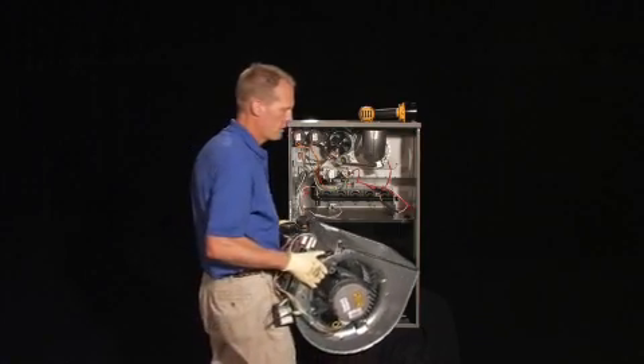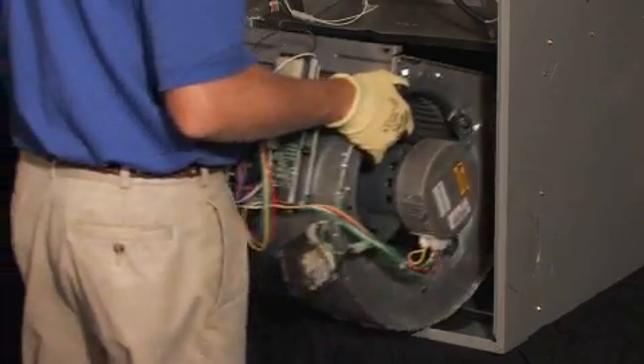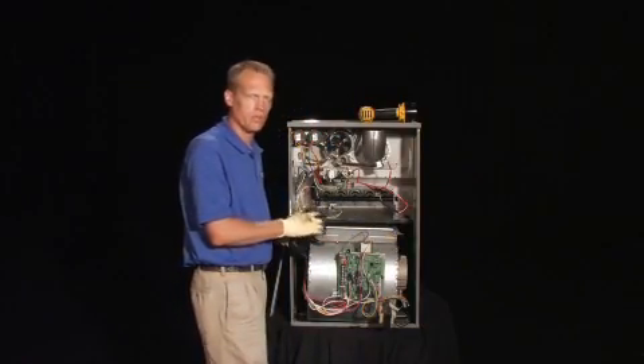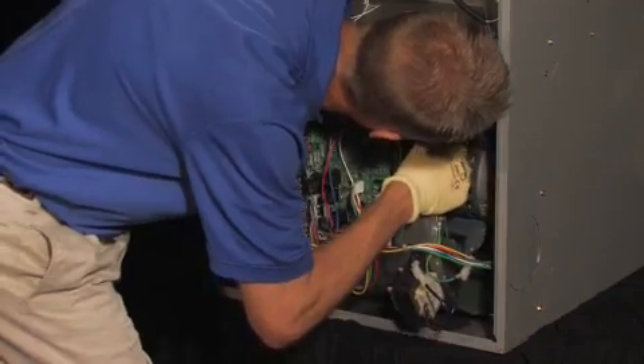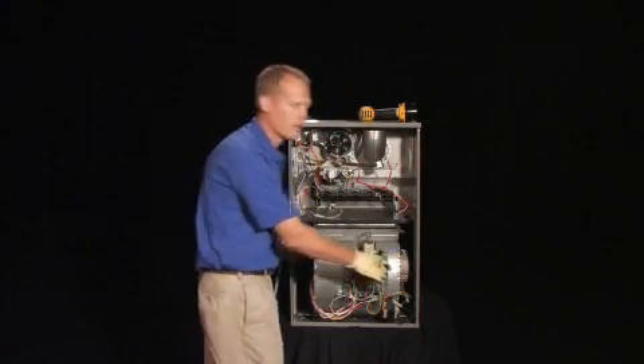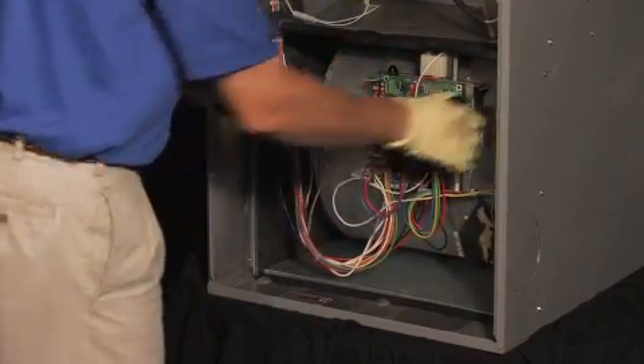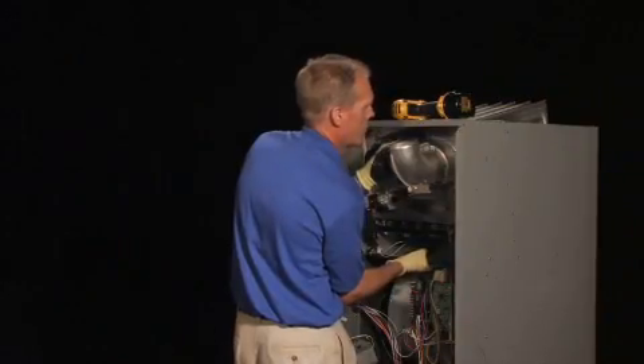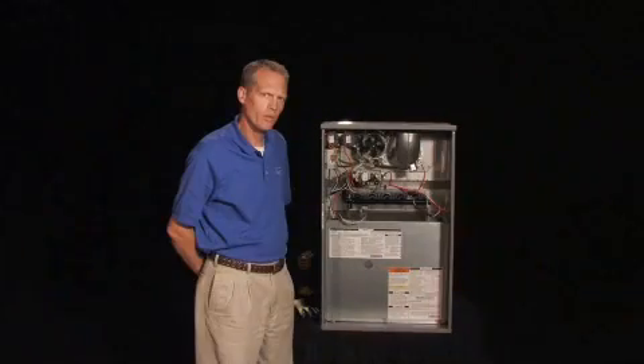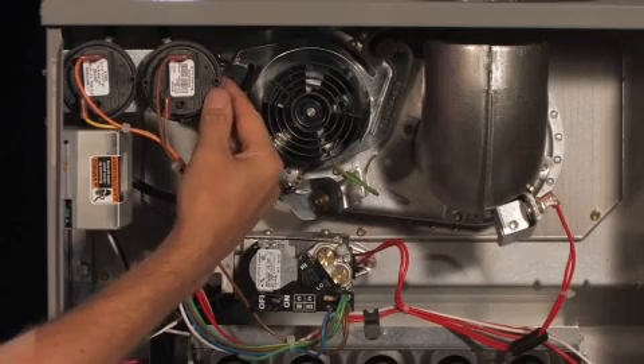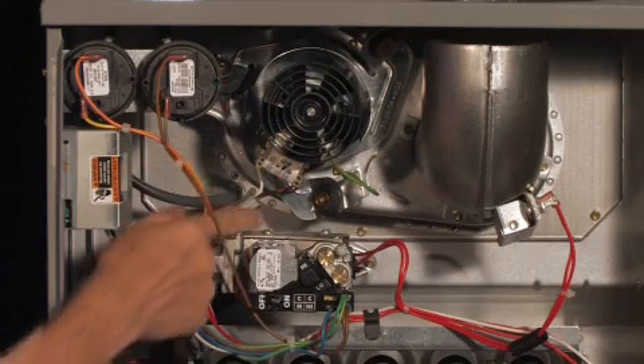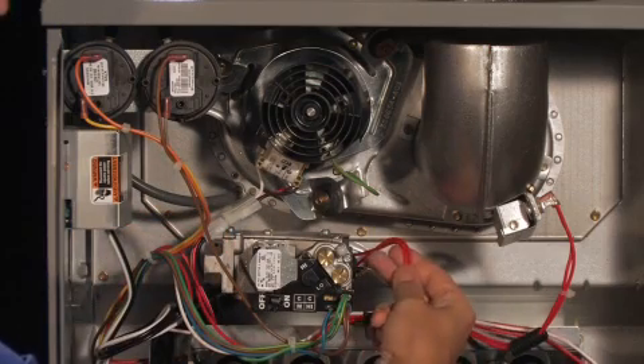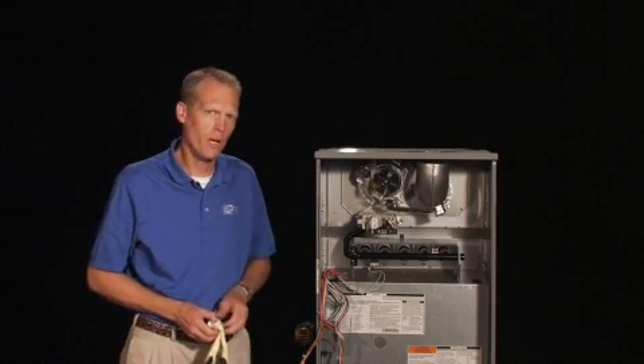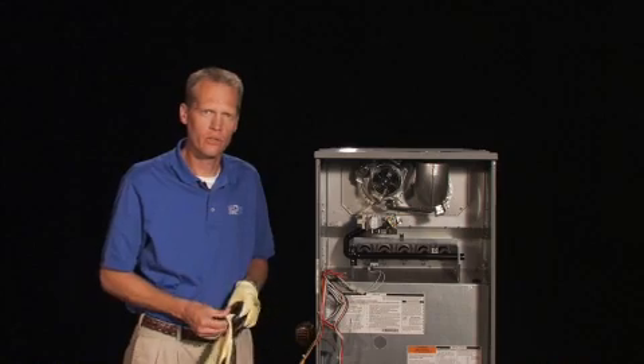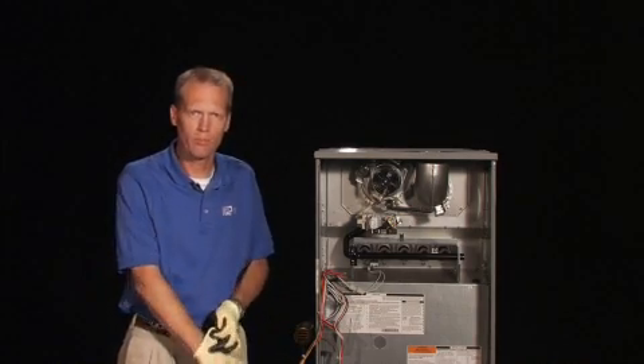To replace, twist the assembly back into position, and with it resting on the base of the furnace, position the rails, then slide it back into place. And it's almost that simple to remove the heat exchanger. To remove the heat exchanger, first we'll unfasten the pressure switch bracket, the junction box, the component connectors, the limit switch wires, and the gas valve wires. We have the pressure switch bracket and the junction box removed. We have all the wire connectors disconnected, wires removed from the components.